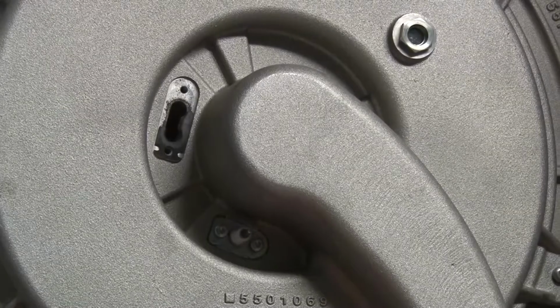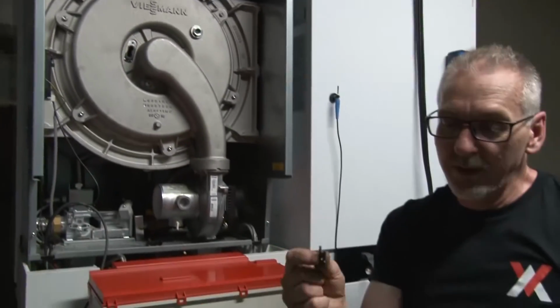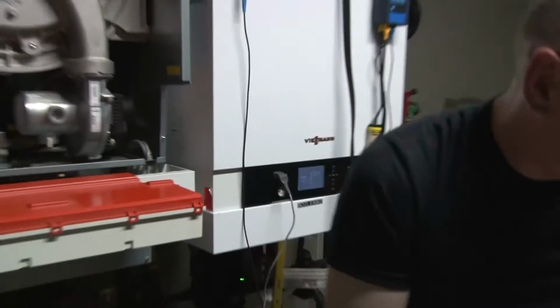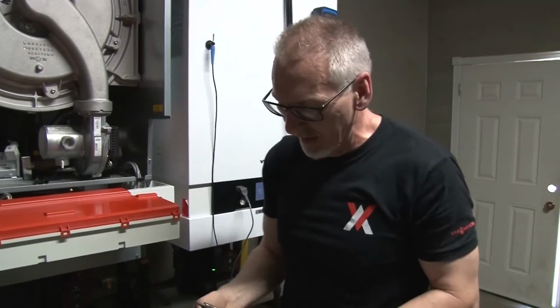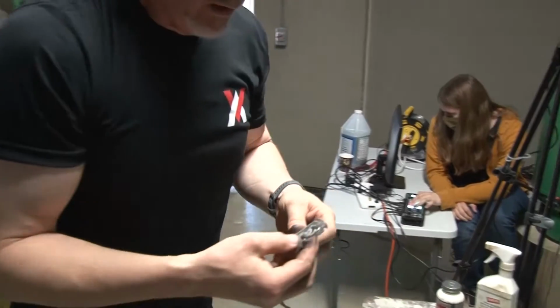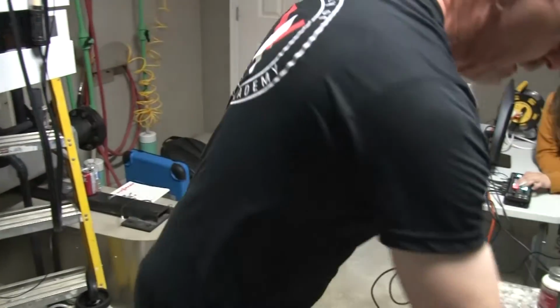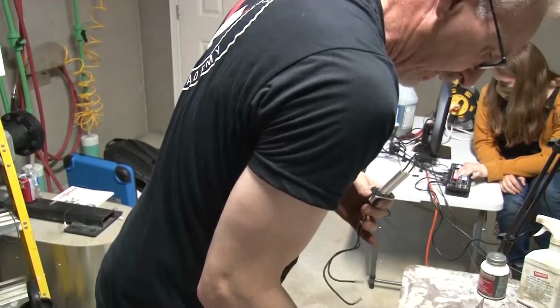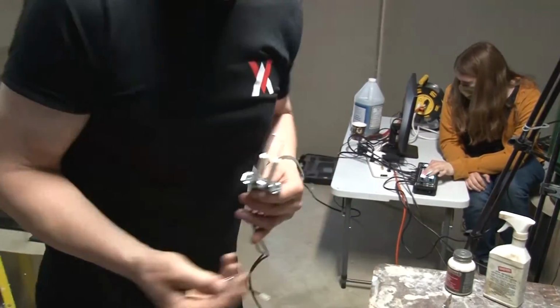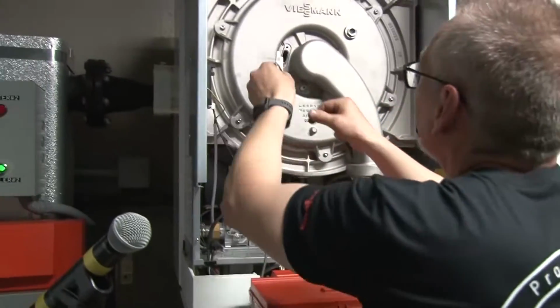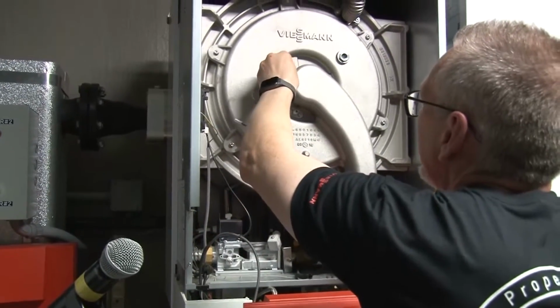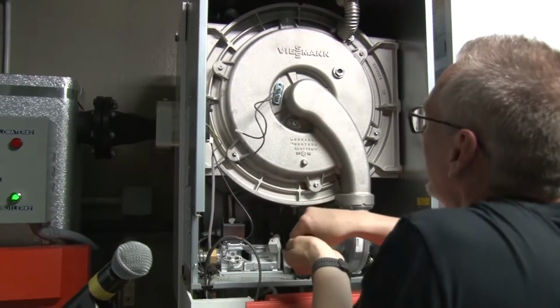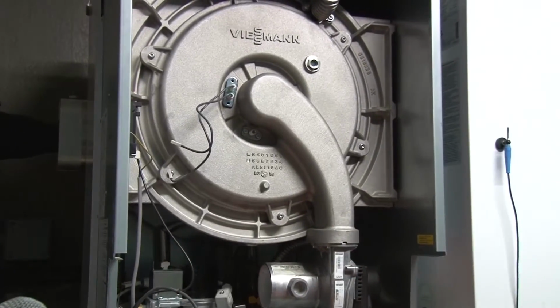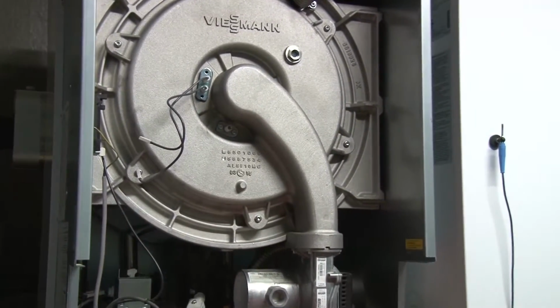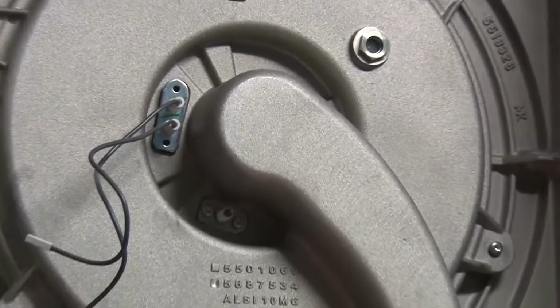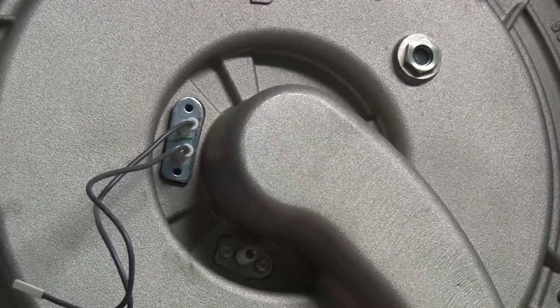I can't reuse this gasket, it's broken, so I need to replace that. So I'm going to have to scrape that stuff off there to make sure that I've got all that removed. We'll slide the new electrode in. I've got the fresh screws with it here, and we'll just slide this back in. Now there's only one way these will go in. If I try to put them in the other way, they're not going to go in. We want that angled back towards the burner. Otherwise, you're going to have ignition faults because the spark is going to be away from the burner there.